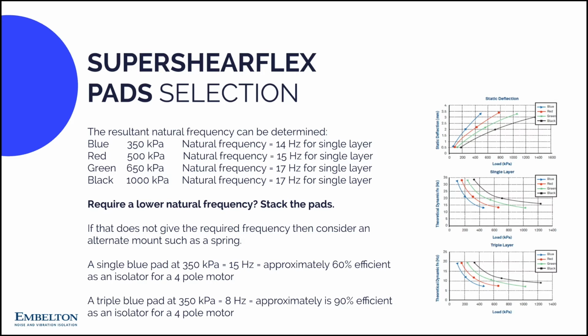If you need a lower frequency to achieve a higher isolation efficiency, we can stack the pads with a layer of aluminium between each pad. See, a single pad is approximately 60% efficient, while a triple pad is approximately 90% efficient while isolating a 4-pole motor.